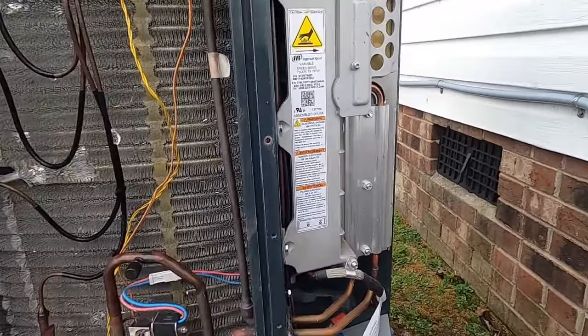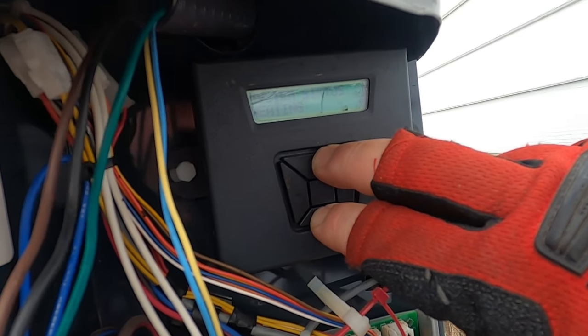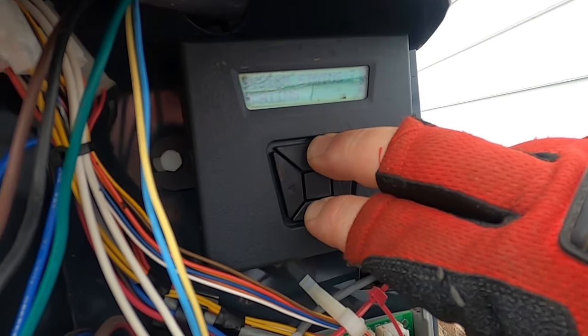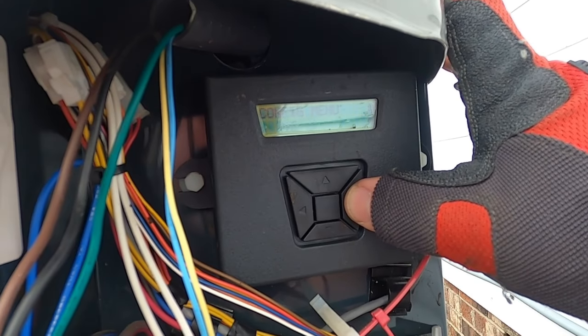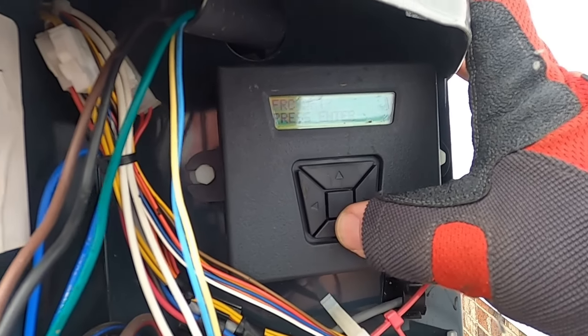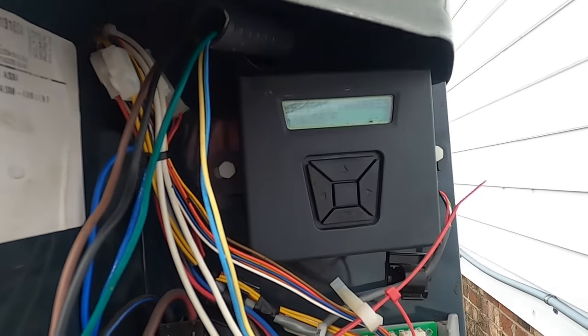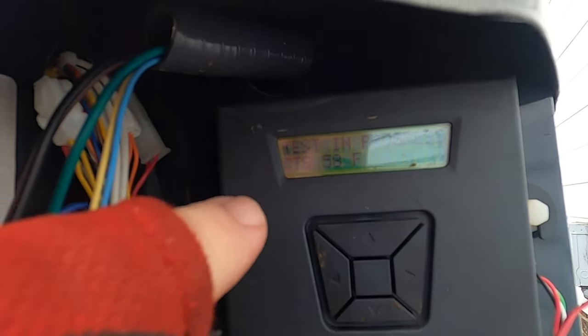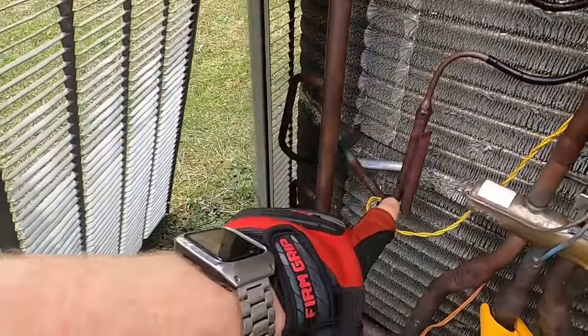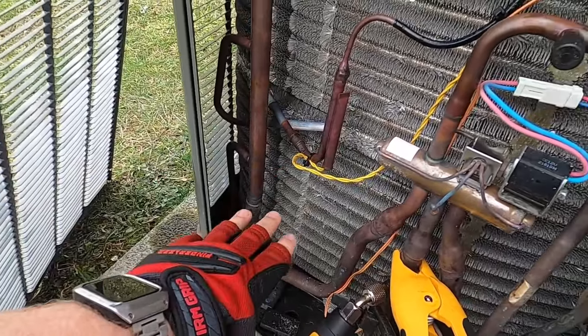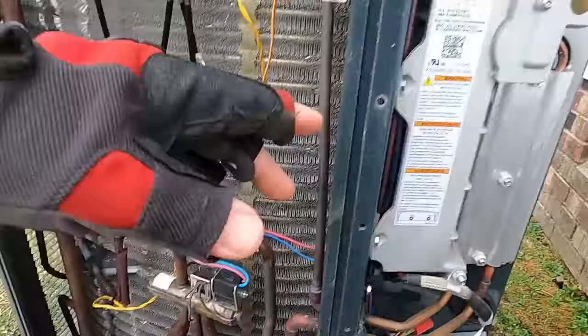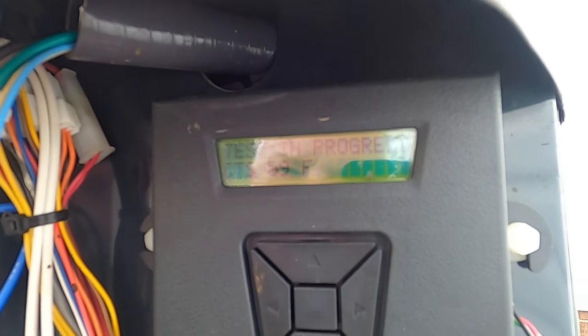Anyway, I'm going to run the defrost real quick on this. Let's do a forced defrost test. So you're going to go in here, hold the up and down arrows down for 10 seconds, and you can get into this thing. I'm going to go to the control menu, go down here to force defrost and hit enter. You can hear it slowing down, so it's going to go into a defrost, and then it's going to be reading the temperature on this coil while it's in defrost. And once the temperature of this coil reaches the termination point, it's going to come out of the defrost cycle. And that's showing you the temperature on that coil right there.